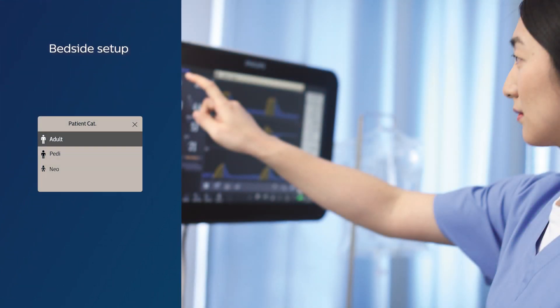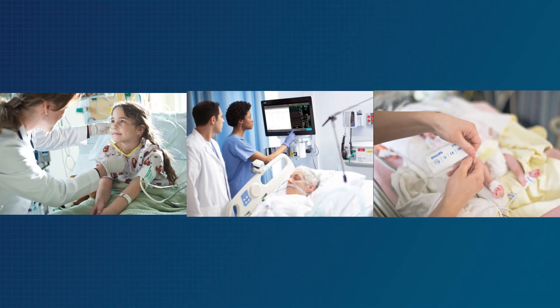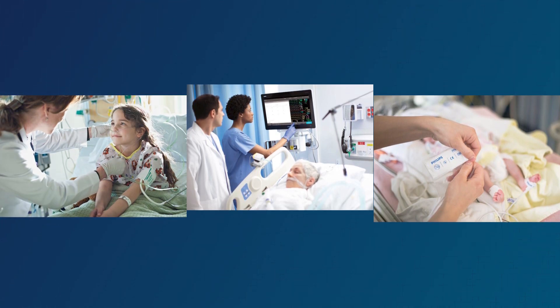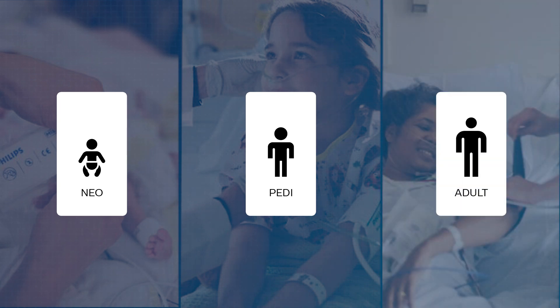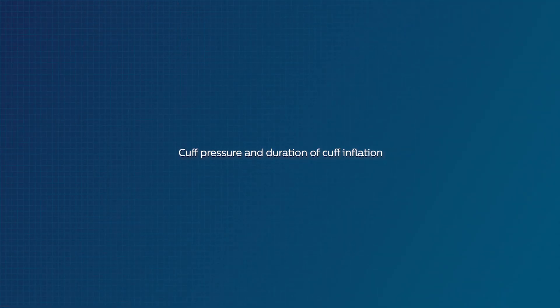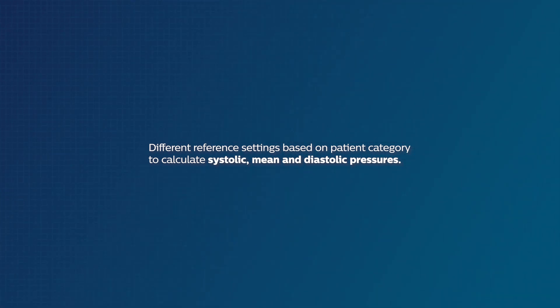Bedside setup for NIBP measurement begins with selecting the patient category for your individual patient. Ensuring patient category is set correctly is imperative because different patient safety limits are applied to neonatal, pediatric, and adult patients. These limits include the maximum cuff pressure and duration of cuff inflation. In addition, monitors use different reference settings based on patient category to calculate systolic, mean, and diastolic pressures.